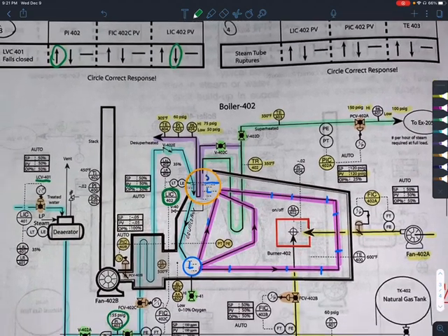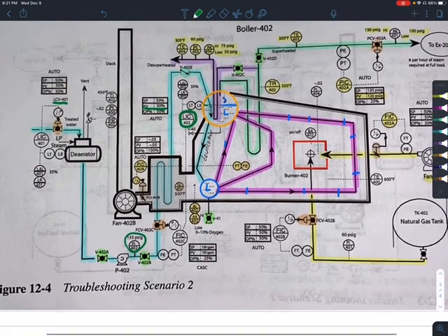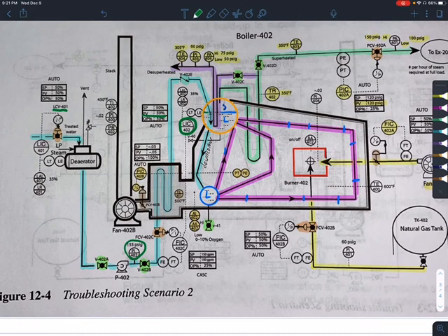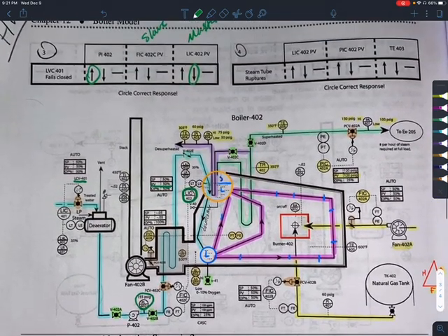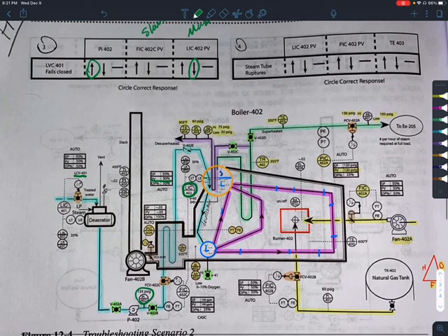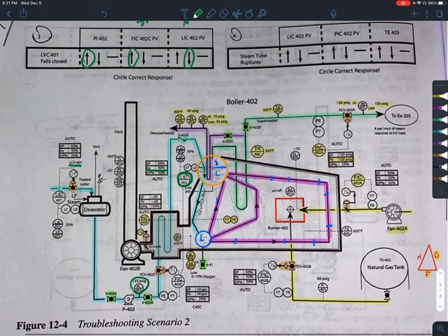Yeah, 402C process variable, sorry. It's going to say, hey, we need more flow. There's not enough level, right? Our alarm is about to go off. LAL 402 is saying, hey, 35%, we need more. So it's going to talk to the flow indicating controller saying, hey, let's open up that valve. So the FIC is actually going to open up more, which is what it's doing. So that's going to go up.